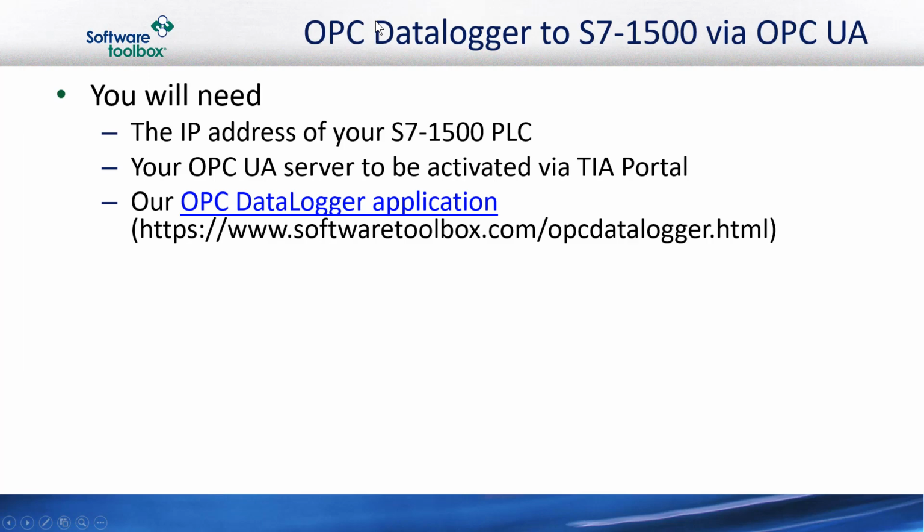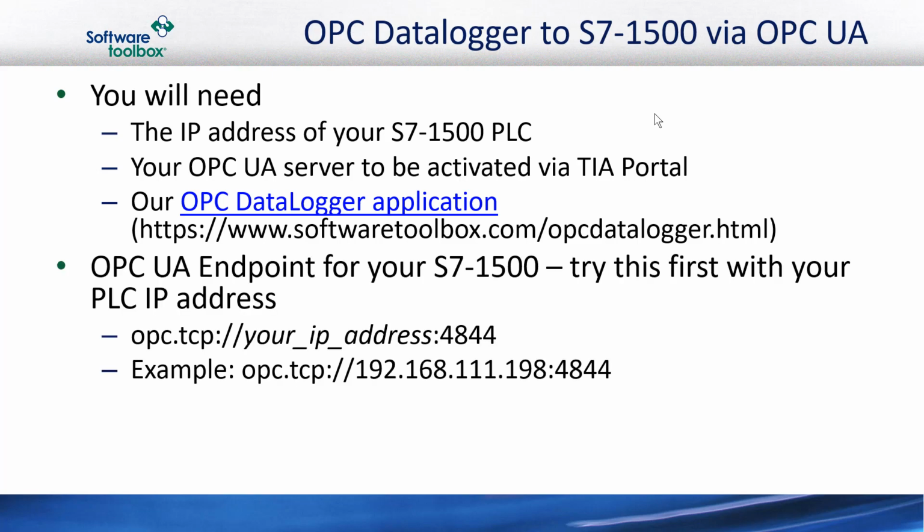First thing you're going to need is the IP address of your S7-1500 PLC. Your OPC UA server will have to be activated in the PLC via TIA Portal. And of course, you'll need our OPC Data Logger application installed, which you can download from the link shown here. You'll need to know the OPC UA endpoint for your S7-1500.